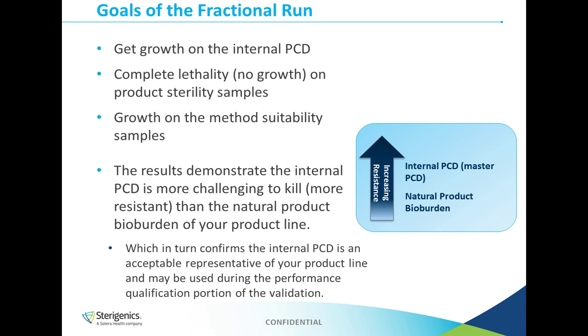And so now that we move forward with the fractional run, some of the goals are you want to get growth on that internal PCD. You also want to get complete lethality or no growth on the product sterility, and you want to get growth on the method suitability samples after they're inoculated with a known organism. Now the thing to point out here is that you need to have growth on that internal PCD so that you can have something to compare to the product sterility.